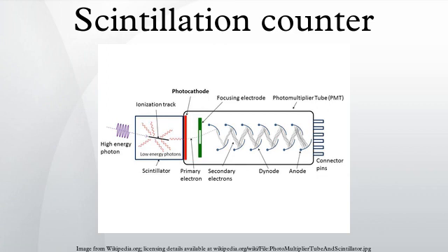and a circuit for measuring the height of the pulses produced by the photomultiplier. The pulses are counted and sorted by their height, producing an XY plot of scintillator flash brightness versus number of flashes, which approximates the energy spectrum of the incident radiation with some additional artifacts.